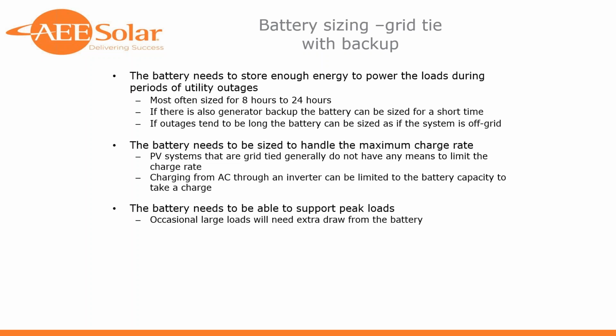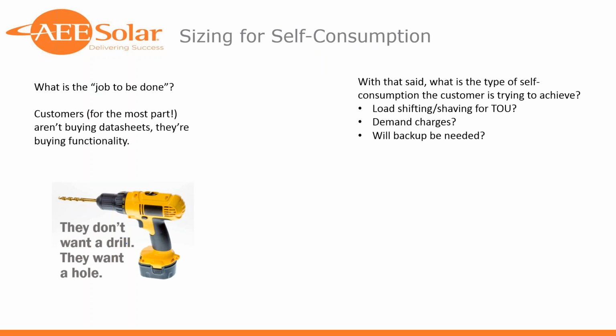So that's backup. We've gone through off-grid, we've gone through backup sizing. We'll speak a little bit more later on some specific chemistries, but I really wanted to take some time now to transition to some of the blossoming applications we're seeing in solar plus storage, which is going to be everything around self-supply, self-consumption. And we've intentionally left a couple of descriptions and definitions out because there's so much overlap in vocabulary on these applications, where one manufacturer will call it one thing, another manufacturer will call it another. You hear people talk about self-consumption, self-supply, load shaving, all related. My takeaway here is we've got to be very specific about what we're trying to do. And that's the reason for this slide.